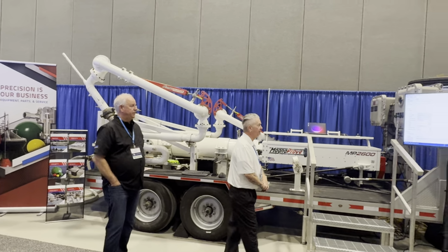On the compact prover, only one prover, the Brooks, has two volumes. They have an upstream and a downstream. Everybody else's volume is the same on the front and the back. So that's why my upstream and downstream say the same thing. It doesn't matter if I'm using upstream or downstream, I don't have to change mine because it's the same calculation. But if you're witnessing something and it's a Brooks, make sure they know if the meter is upstream or downstream from you, so you get the correct calculations. Because it'll come in, but it'll be off because they used the wrong volume. It's just something to witness.